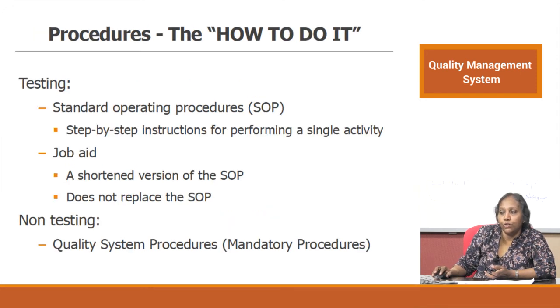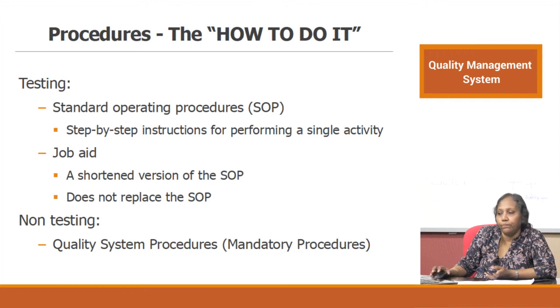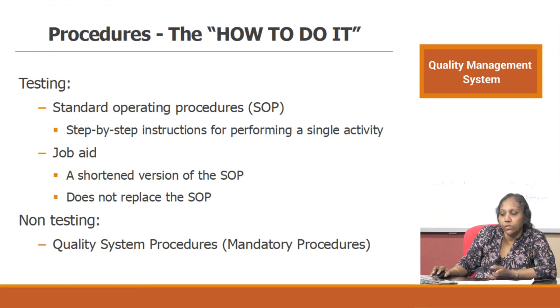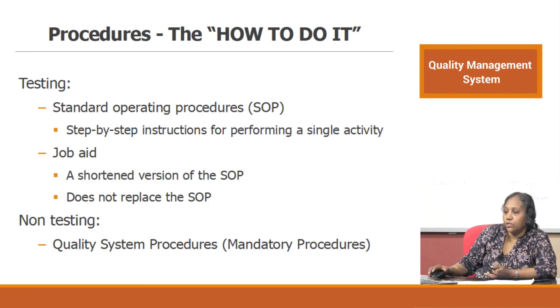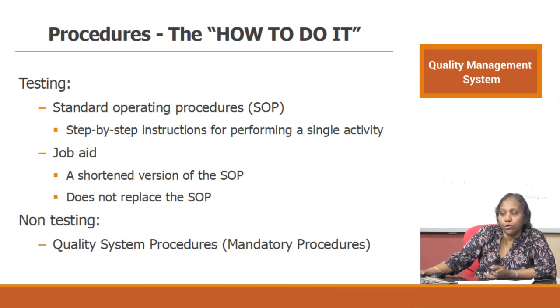Coming to procedures — how to do it. Policies tell you what to do, processes tell you how it happens, and procedures tell you how to do it. Testing procedures are generally depicted as standard operating procedures (SOPs) — a step-by-step instruction for performing a single activity. A job aid is a shortened version of an SOP. Non-testing procedures are called quality system procedures, mandatory procedures, or just procedures. So there are two kinds of how-to documents: testing (SOPs) and non-testing (procedures).